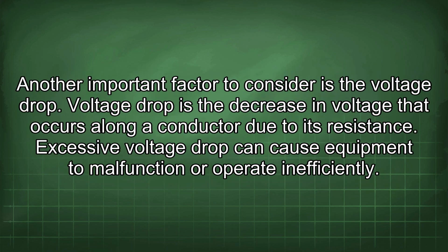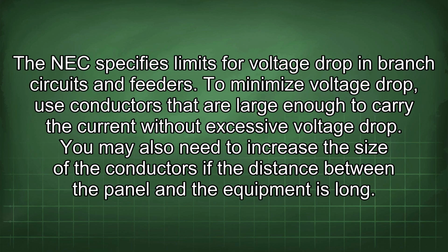Another important factor to consider is the voltage drop. Voltage drop is the decrease in voltage that occurs along a conductor due to its resistance. Excessive voltage drop can cause equipment to malfunction or operate inefficiently. The NEC specifies limits for voltage drop in branch circuits and feeders. To minimize voltage drop, use conductors that are large enough to carry the current without excessive voltage drop. You may also need to increase the size of the conductors if the distance between the panel and the equipment is long.